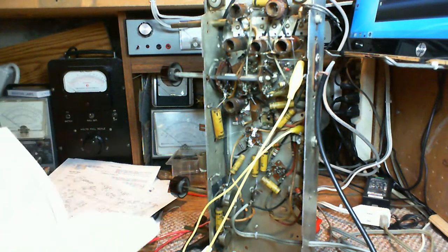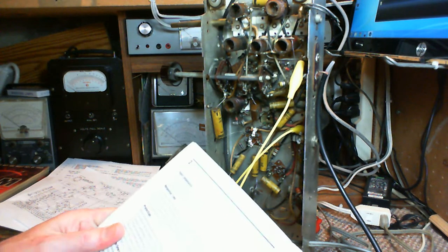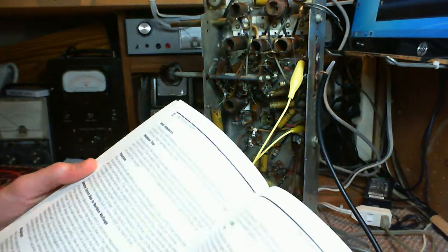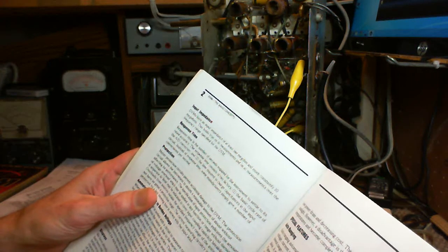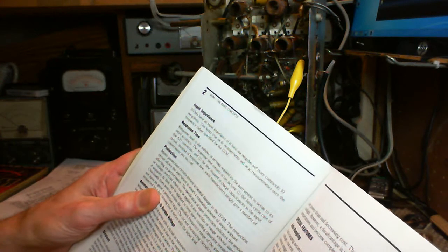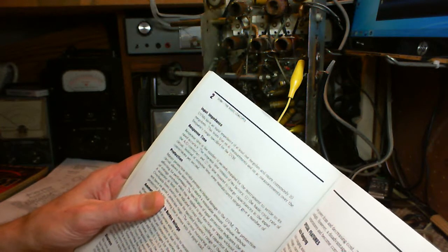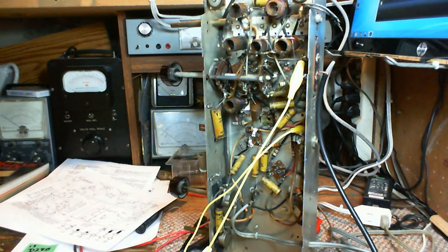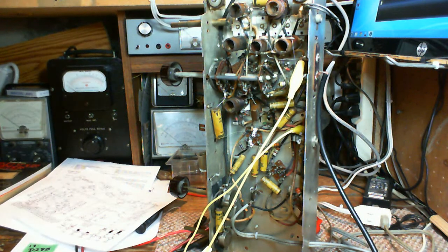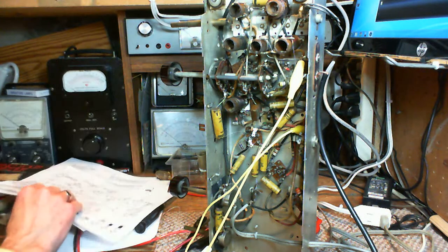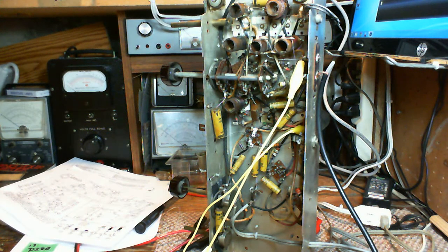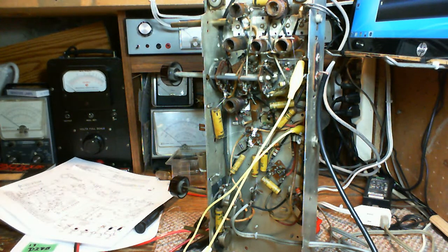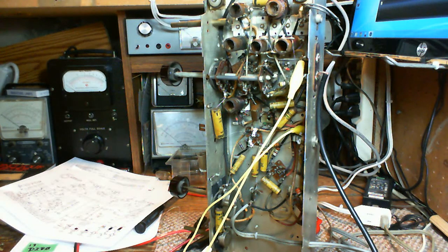This book has this line in it, and this is what I've been reading all my life and what I'm going to try to prove to myself here. Under digital voltmeter: DVMs have an input impedance of at least one megaohm and more commonly 10 megaohms. This holds true on DC measurements and on AC measurements over the frequency range specified for the DVM. That's what I always thought. I've just always assumed it's a very high input impedance on those meters.